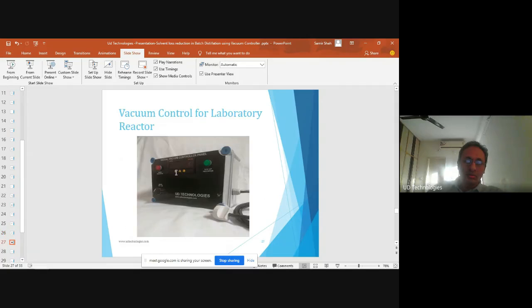So this is the photograph of our digital vacuum control panel. It is for the small laboratory reactor or evaporator, where you have to keep it between the vacuum source, the vacuum pump, and the reactor, and you have to set the vacuum here in the vacuum controller. It will control the vacuum depending on the set point and give you the controlled vacuum to the reactor, which will have a better condensation.